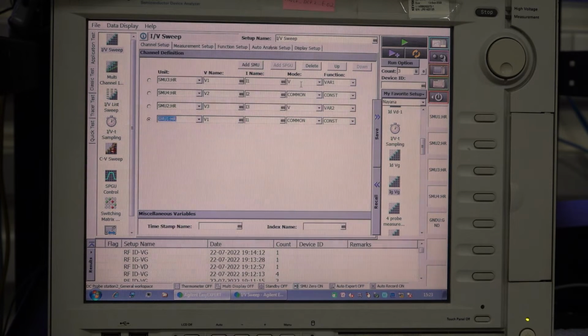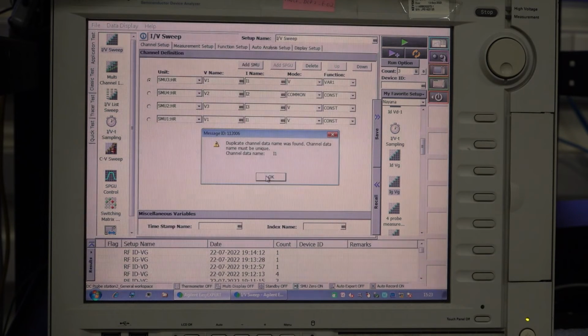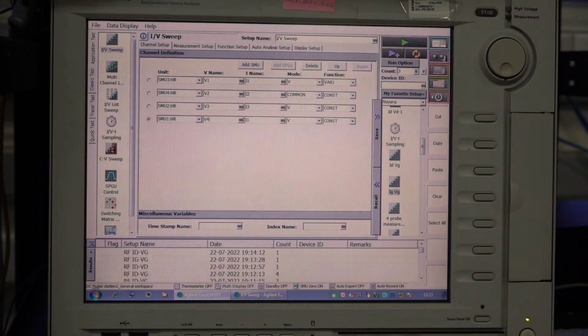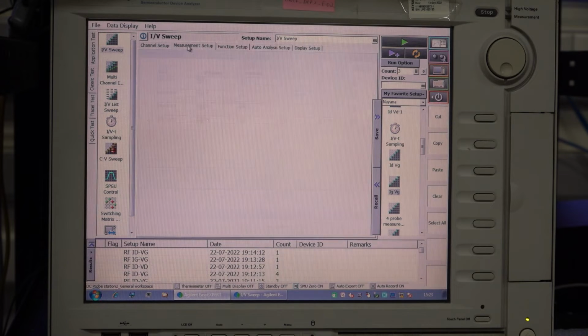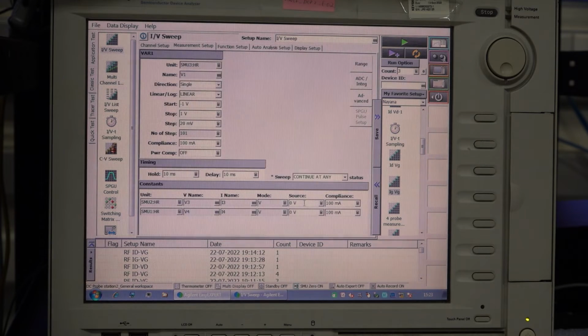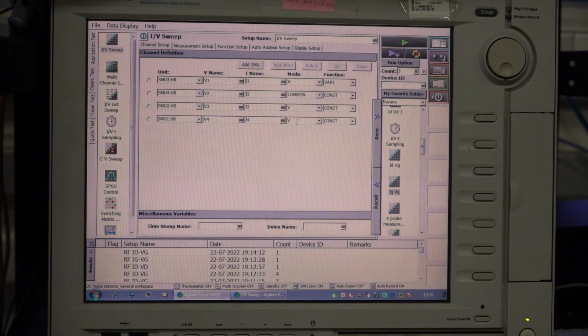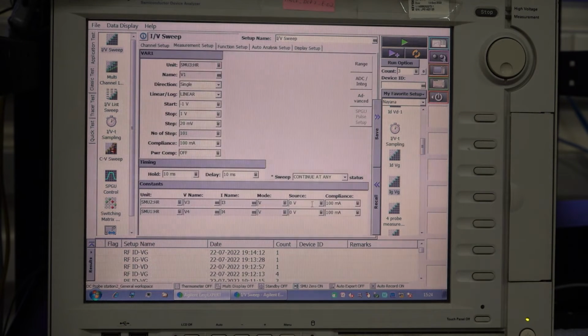So these two SMUs are for voltage. If you want to measure a current, we can select a voltage here and a voltage here. We can give constant here, because we need a current measurement. One second, we will change the SMU name because the error popped up. So we can select the current here for these two, we can select the voltage here for these two SMUs, and then we can give a 0 volt here so that the instrument can measure a current. Now the voltage whatever we give, it is a sweep voltage -1 to +1, it will remain the same, and the current will be measured across these two terminals.